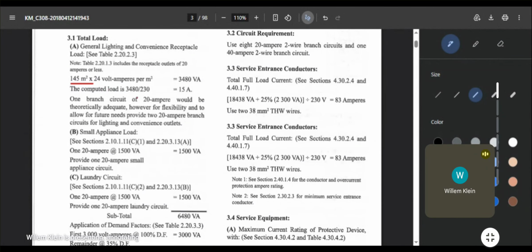Okay? And then your computed load is 15 amperes for 230 volts supply. So that's 3480 VA divided by 230 volts. So you will have 15 amperes. So again, one branch of 20 ampere could cover both the general lighting and convenience. But again, for flexibility and convenience purposes, and for future needs also, you can separate the two, with two 20 ampere branches for lighting and convenience outlets separately.